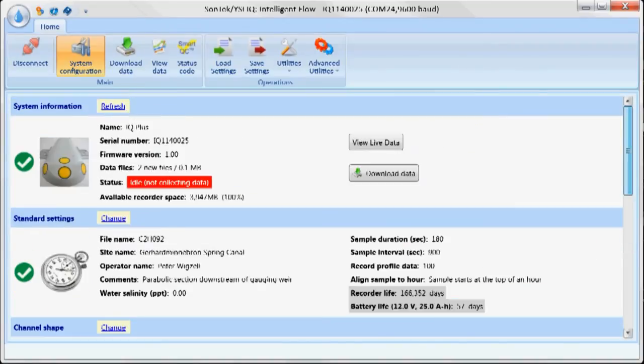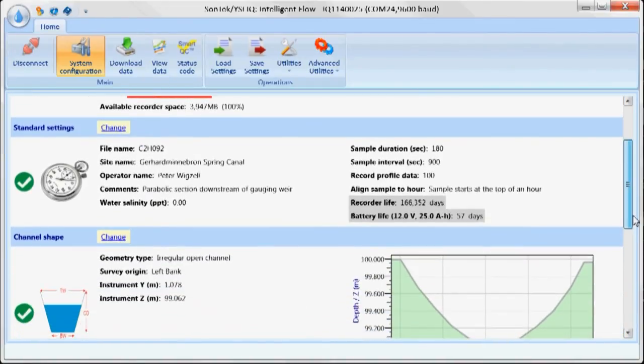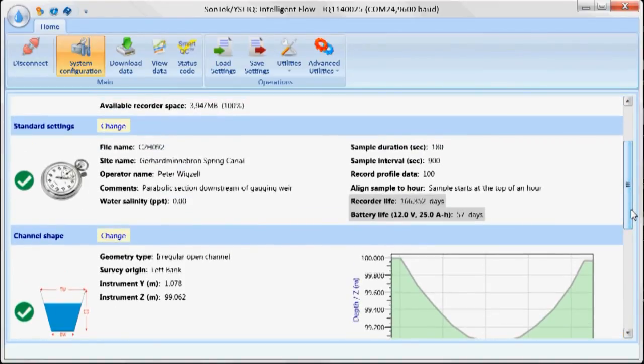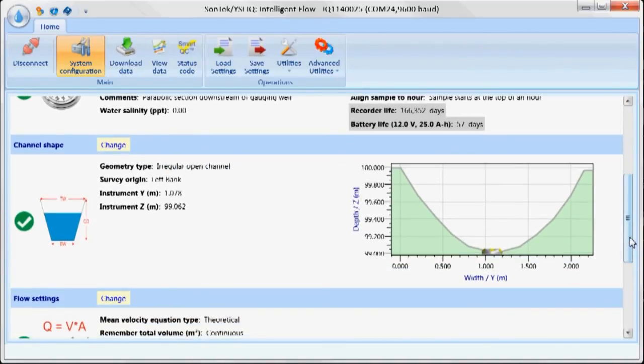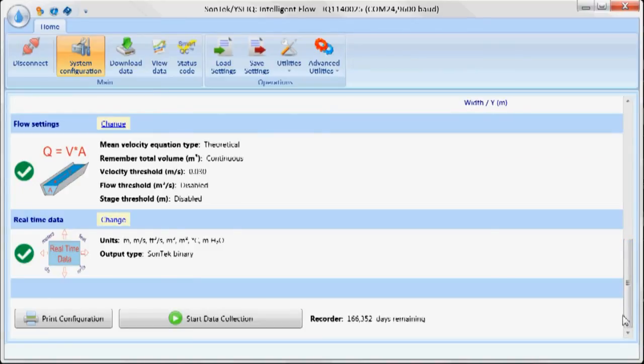When we connect to the instrument, it's going to give us the system information. For the settings, we're going to tell it the file name and the site name, the operator, where we're at. Also, we're going to set the duration of the sample and the interval. The next thing that we have to change is actually the type of channel shape that we're going to use. There's a variety of different types of channel shapes where I can input my own surveyed value. The next thing is I'm going to program the instrument about how to do the flow calculation. There's two basic calculations: one is theoretical, which in most cases you'll be using, it doesn't require a calibration, or a velocity index.